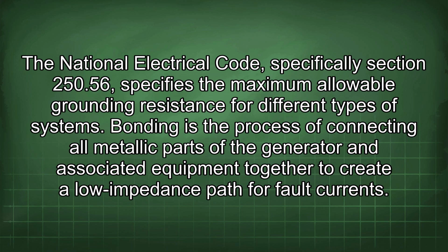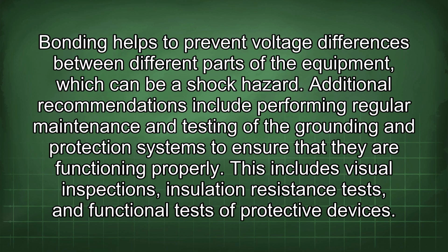Bonding is the process of connecting all metallic parts of the generator and associated equipment together to create a low impedance path for fault currents. Bonding helps to prevent voltage differences between different parts of the equipment, which can be a shock hazard.